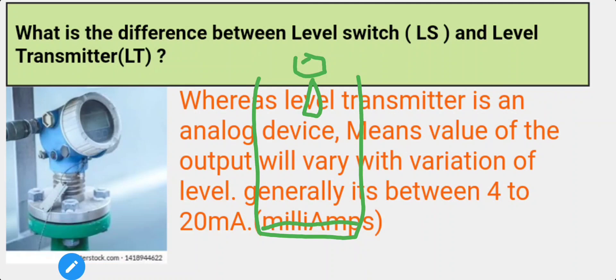Like if there is a low level, it will give you 4 milliamps output so that in control system we will get the value as zero. Or whatever its high value like this, then the transmitter will give you 20 milliamps.